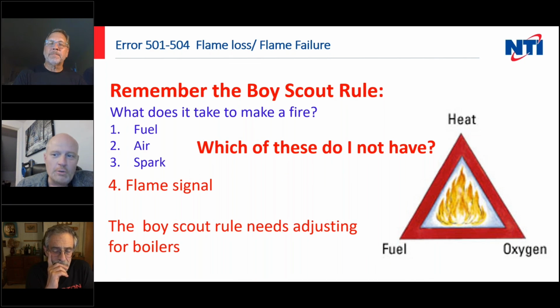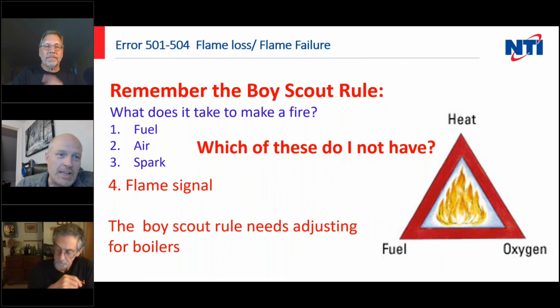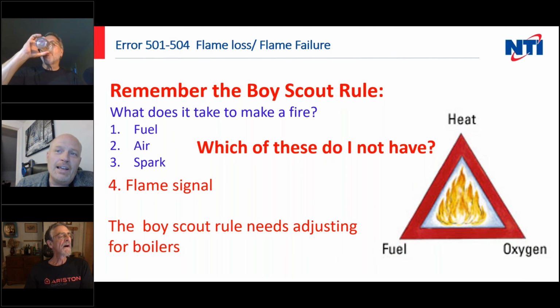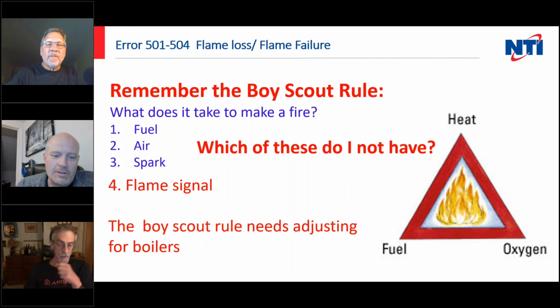I always ask my new trainees and recruits, when do you stop building a campfire? And nobody ever has an answer to it because they don't even realize what they're doing. But the answer is you stop building your campfire when you see smoke and flame and whatever, because that's flame signal. Well, the boiler sees flame signal via the flame rod. It may be burning perfectly, but if it doesn't see the flame, it doesn't matter. It's going to shut down. So when you have a boiler, you need that flame signal. So really it's a fire square when it's a boiler, because you have to have flame signal.